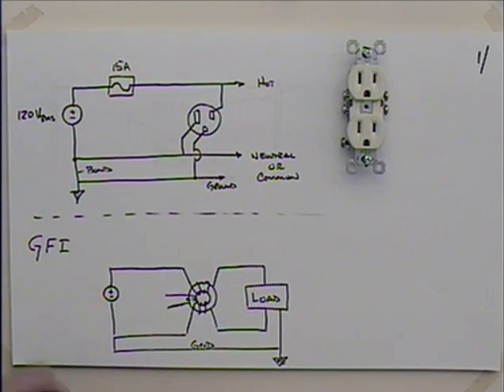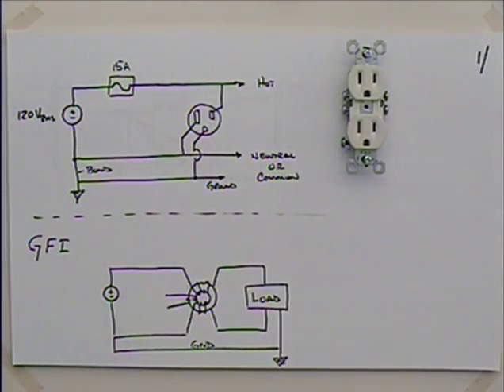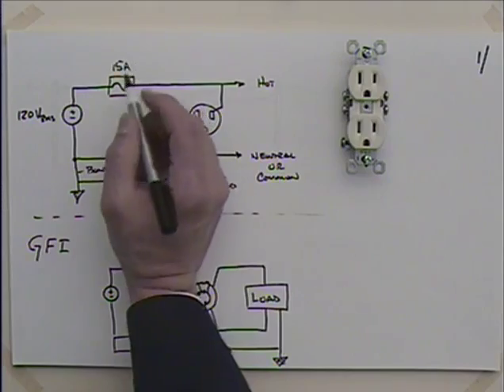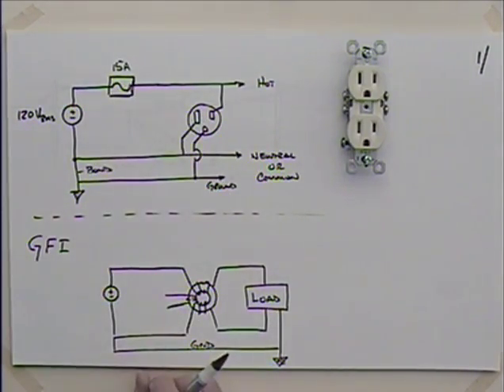We looked at a case where you had a fault in the appliance, some sort of short or something wrong, and while that ground path was important so it didn't go through the user, this circuit breaker, this fuse up here, is really just to protect the wiring because we know that 15 amps is more than enough to cook you.